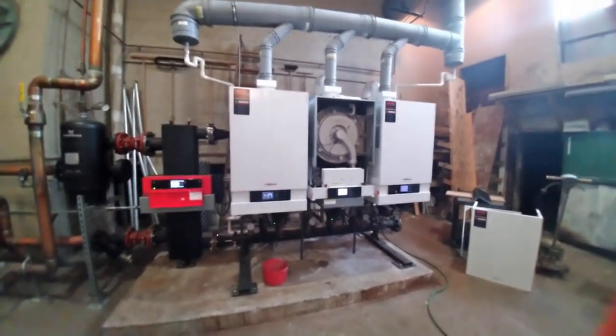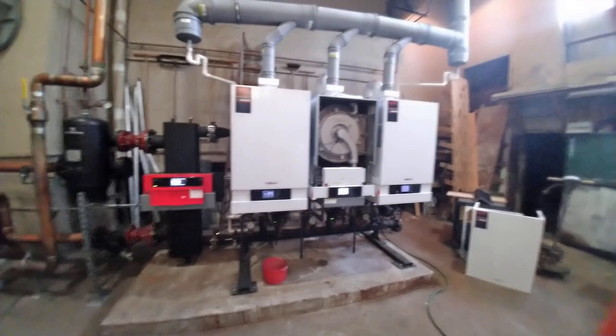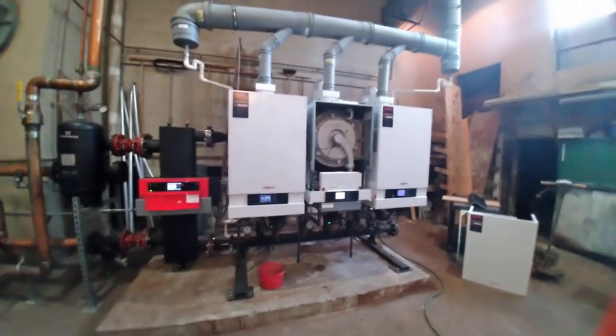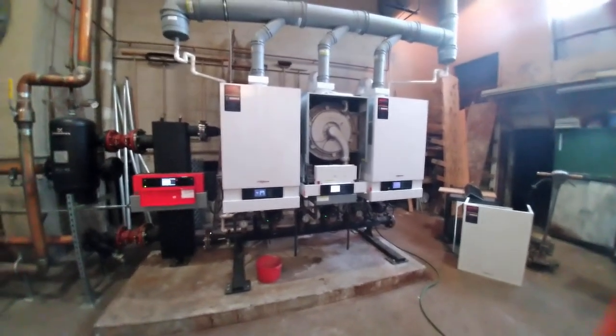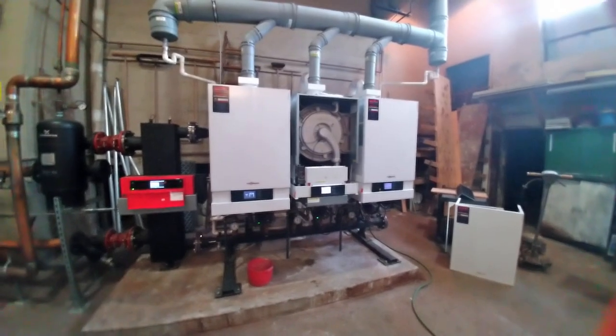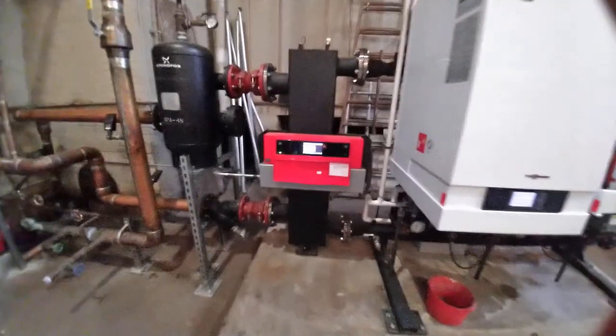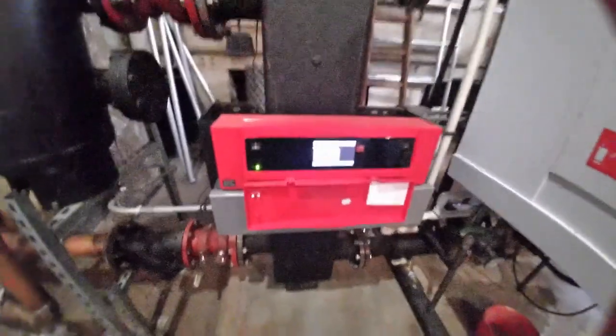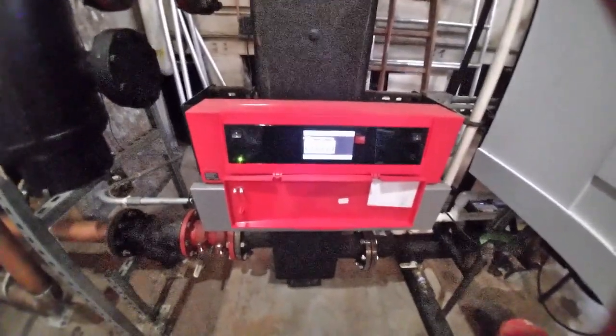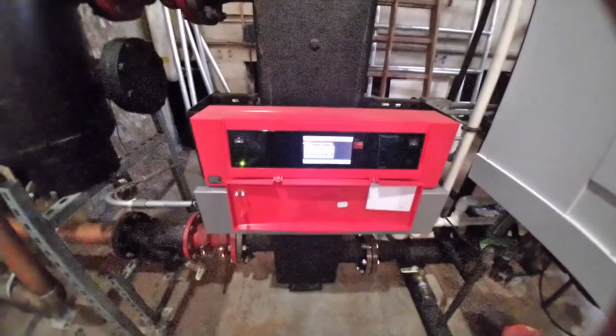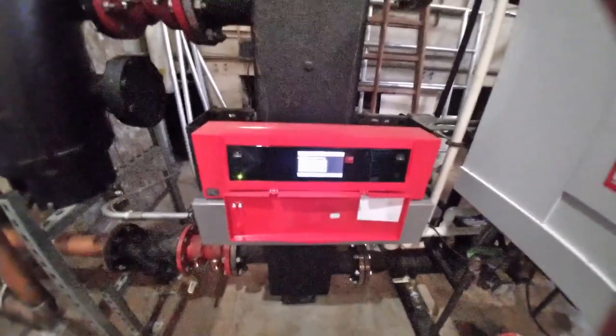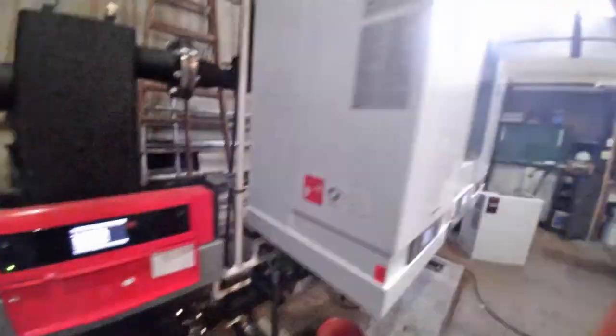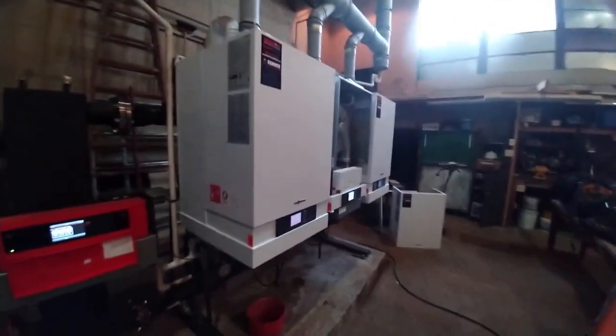And not that they run at high efficiency all the time, it is a 180-degree water system, so we don't figure 95% on the coldest day of the year. But according to our modulation control, even on a cold winter day at approximately 15 degrees out, we've been down here and these things are cruising along and modulating up and down at roughly a 400,000 to 500,000 BTU input.